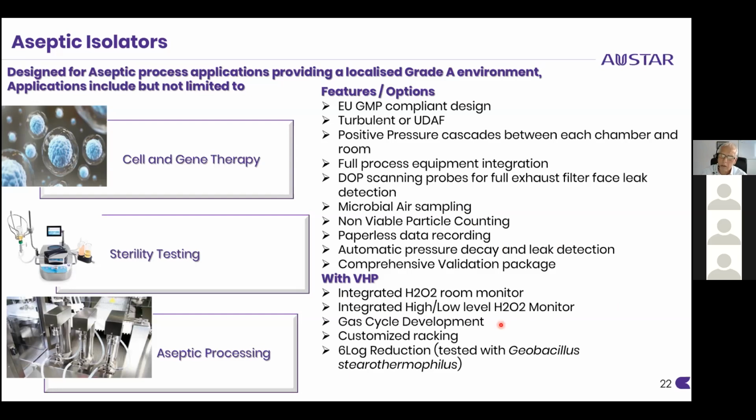We offer gas cycle development, so specific to any client's product, process and load, we will do that gas cycle development alongside our end user, and at the same time train him on how to do gas cycle development. We would offer custom racking, and obviously 6-log reduction testing is part of the gas cycle validation.